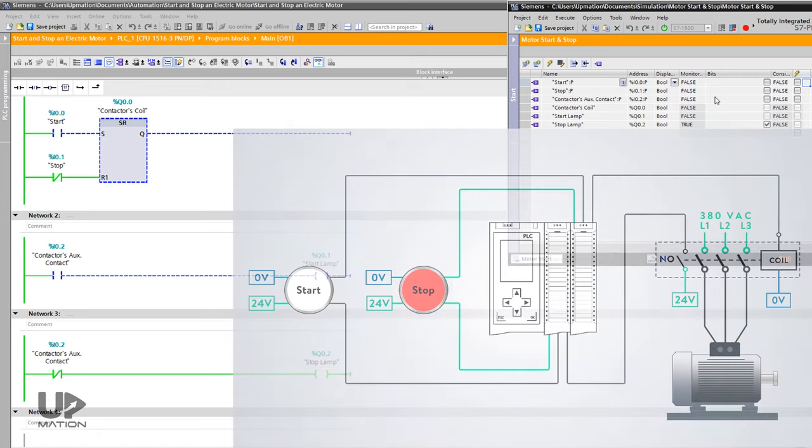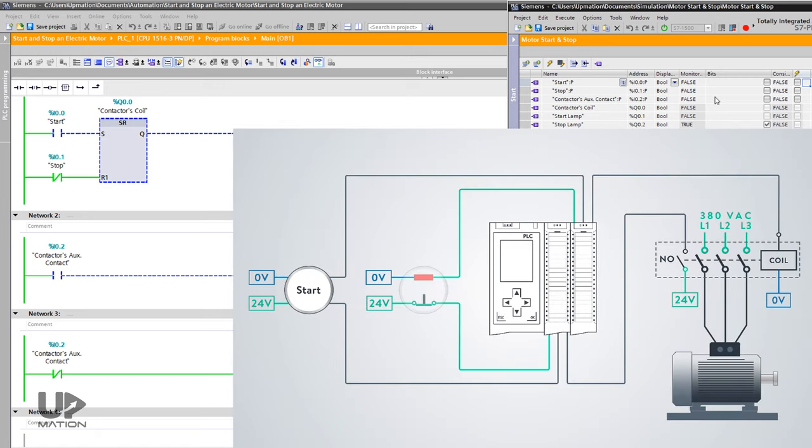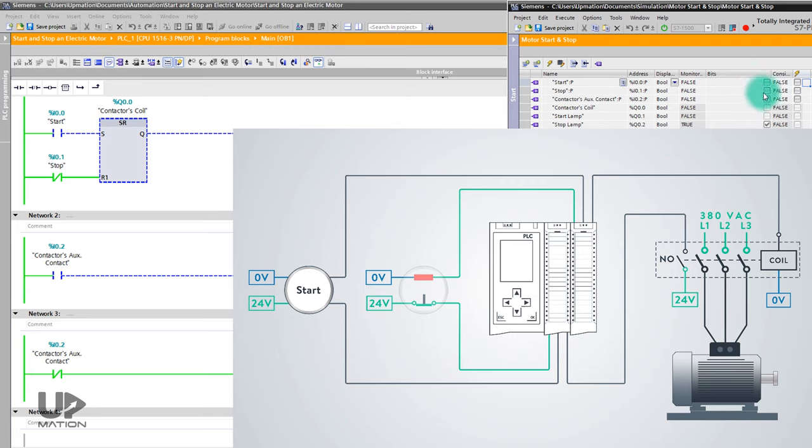As I explained, the stop push button has a built-in normally close contact. And in the normal condition, when it's not pushed, it sends the 24V DC signal to the PLC's input card. So I simulate its input to 1. The start lamp is off and the stop lamp is on, and that's okay.